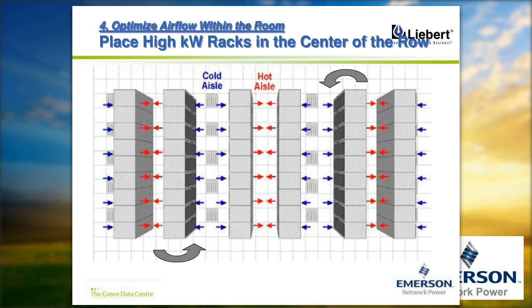Now, many times the customer has some low density, some medium density, and some high density racks. It is good to have, from a CFD perspective, the high KVA rack or high kilowatt rack at the center of the row, so that it can be cooled properly from both sides and there won't be any challenges with respect to hotspots.